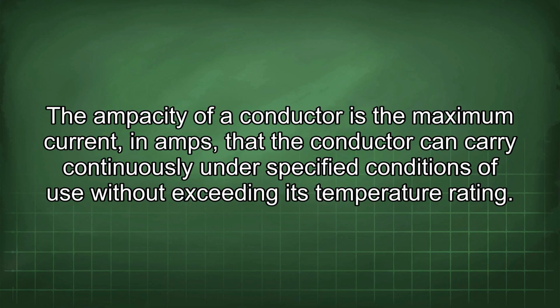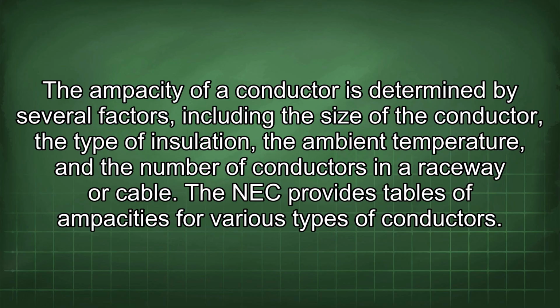The ampacity of a conductor is the maximum current in amps that the conductor can carry continuously under specified conditions of use without exceeding its temperature rating. The ampacity of a conductor is determined by several factors, including the size of the conductor, the type of insulation, the ambient temperature, and the number of conductors in a raceway or cable. The NEC provides tables of ampacities for various types of conductors.